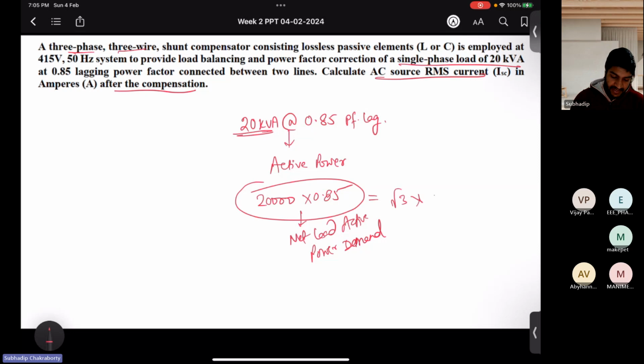Net load active power demand will be borne by the three phases after compensation. So just apply √3 into VRMS into IRMS line to line. So this is 415 into your IS. Agreed? So what is it coming? Okay, 23 amps. 23.65 amps. Yes, yes.